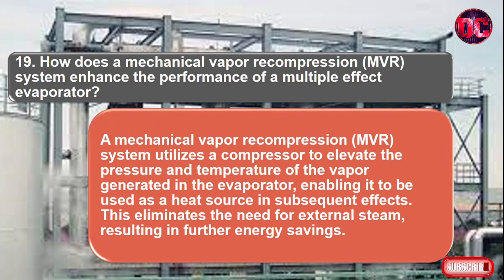How does a mechanical vapor recompression system enhance the performance of a multiple effect evaporator? A mechanical vapor recompression system utilizes a compressor to elevate the pressure and temperature of the vapor generated in the evaporator, enabling it to be used as a heat source in subsequent effects. This eliminates the need for external steam, resulting in further energy savings.